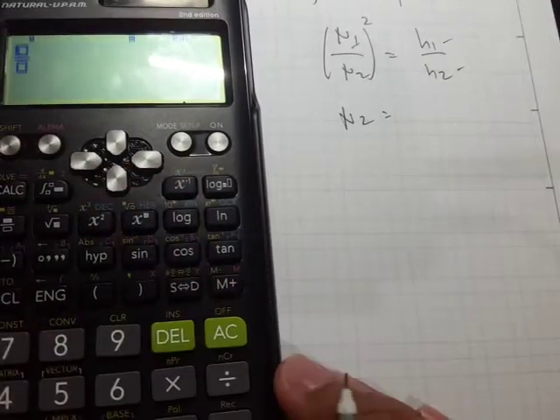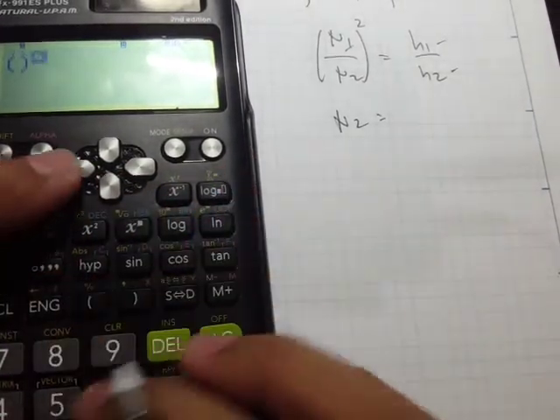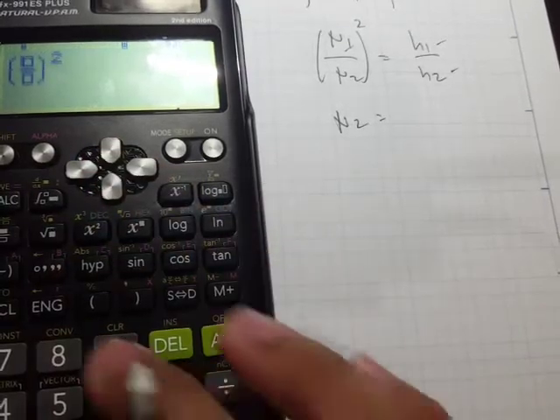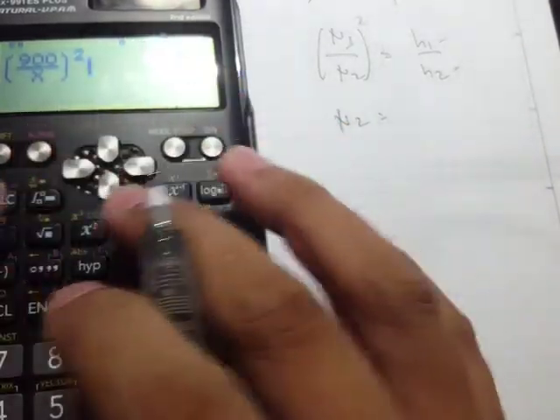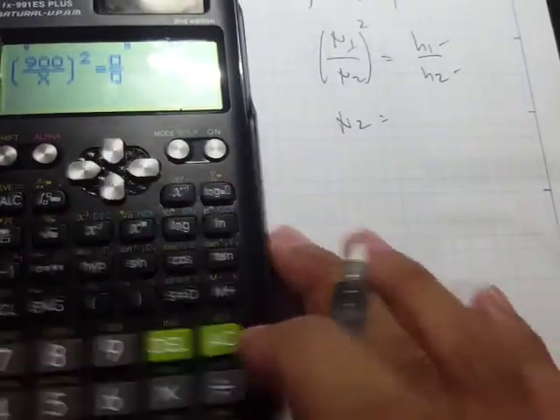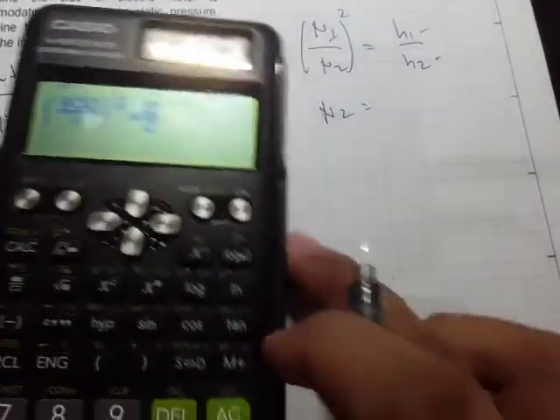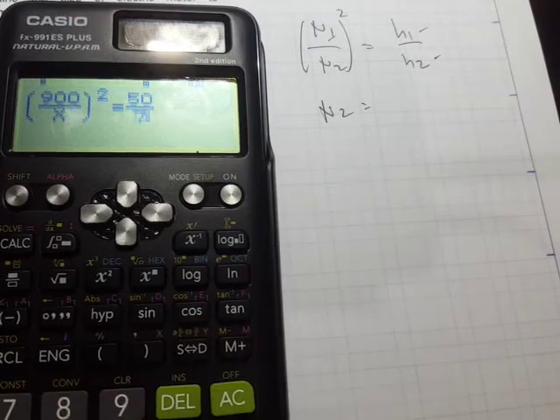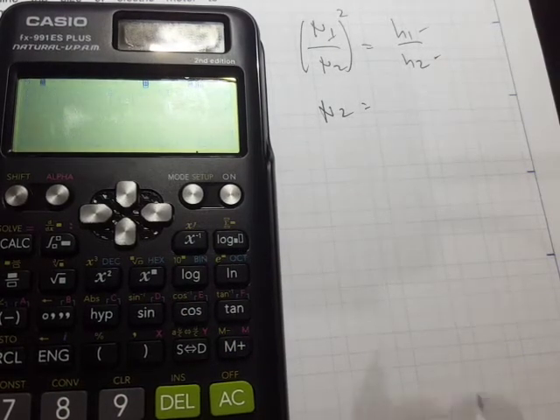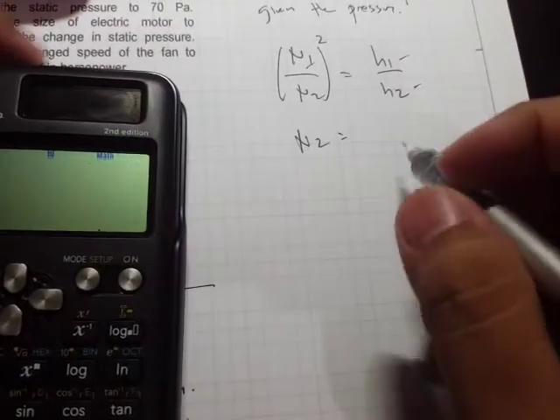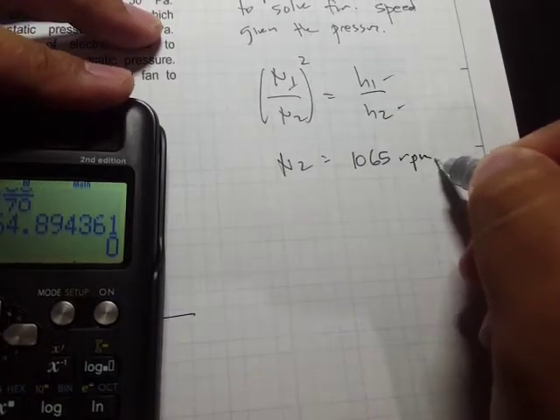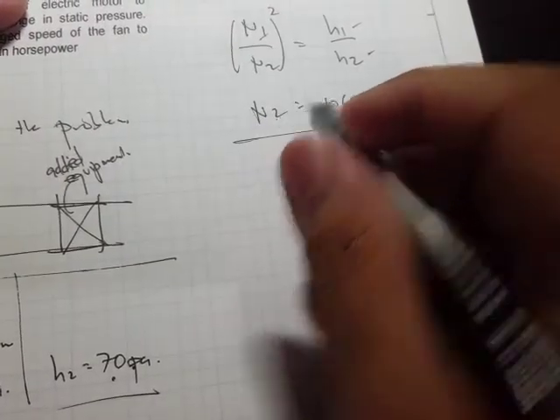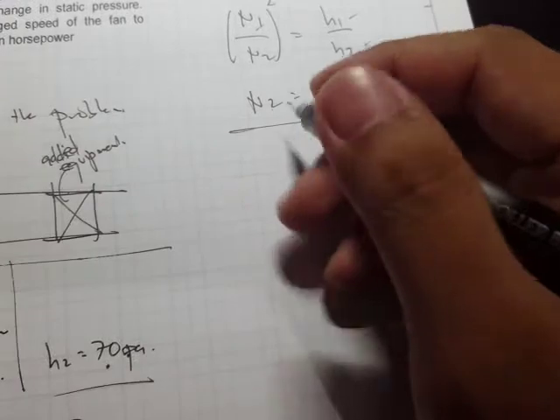Using shift-solve on the calculator: n₁ = 900, h₁ = 50, h₂ = 70. The result gives us n₂ = 1065 RPM. So the new fan speed is 1065 RPM.